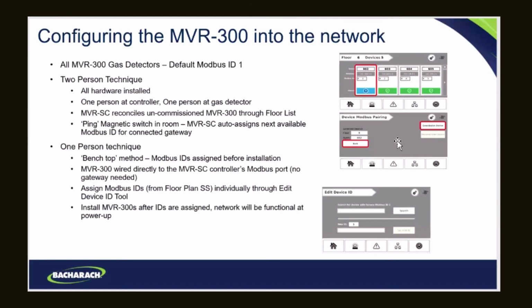You go to the next one that needs to be commissioned, you pull that one up, you make sure that the floor and the device ID are correct, and again, that comes in from that CSV file, and you do a wand ping in the room and a commission device at the controller. So that's the two-person way to do it, and you walk through each one of those rooms, and essentially the controller itself does the commissioning for you.